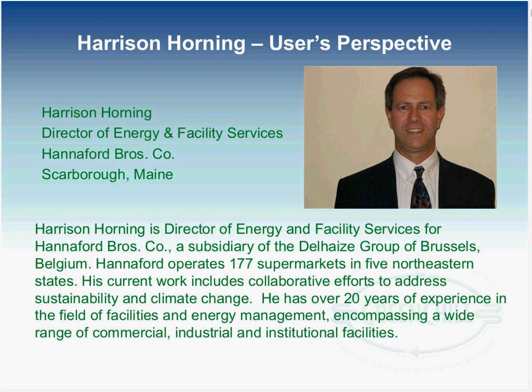There's a lot of experience with this type of technology in the refrigeration world, because we use this type of thing with subcoolers and such, and we're very comfortable with running refrigerant through these things. And quite frankly, we've had good success running water glycol through them too, but you want to be careful and make sure that you don't get any kind of sediment in your water glycol loop that could clog the thing up, because that would be a bad thing. The pump is a critical component. If that breaks, you need to fix it in a hurry, so we keep a spare pump handy, and our guys have all been trained to take that down and get it back up and running in about an hour.